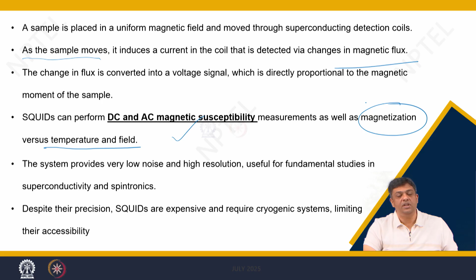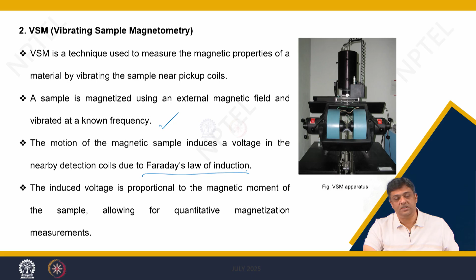The next much simpler and less expensive technique is the VSM, that is the vibrating sample magnetometry. So, what do you do here? You measure the magnetic properties of the material by vibrating the sample near a pickup coil. Now, a sample is magnetized using an external magnetic field, and then it is vibrated at a known frequency. What happens? The motion of the magnetic sample induces a voltage in the nearby detection coils due to Faraday's law of induction. So, you get induction taking place. Very simple. If I ask you a question, what would be the induced voltage? Clearly, the induced voltage would be proportional to the magnetic moment of the sample, and immediately you will be able to quantitatively determine the magnetization in such samples.